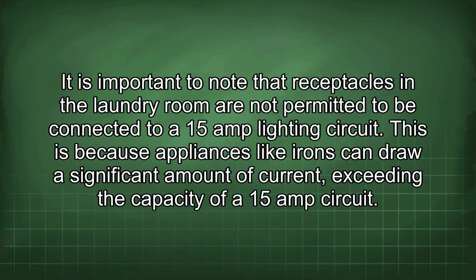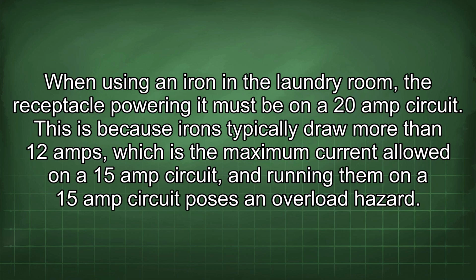It is important to note that receptacles in the laundry room are not permitted to be connected to a 15-amp lighting circuit. This is because appliances like irons can draw a significant amount of current, exceeding the capacity of a 15-amp circuit. When using an iron in the laundry room, the receptacle powering it must be on a 20-amp circuit. This is because irons typically draw more than 12 amps, which is the maximum current allowed on a 15-amp circuit, and running them on a 15-amp circuit poses an overload hazard.